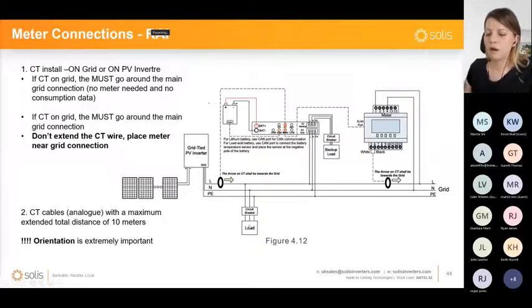This is important only for this reason, to offer the customer the option to monitor his loads. But otherwise, in terms of how the system is operating or charging or discharging, it wouldn't necessarily make a difference, because the meter will be sending this data. So if you don't have the means to install the CT clamp next to the grid-tied inverter, there's no problem if you don't install this CT clamp and you install only the meter. It might sound a little bit confusing, so if you have any questions on this side, it would be a really good moment.